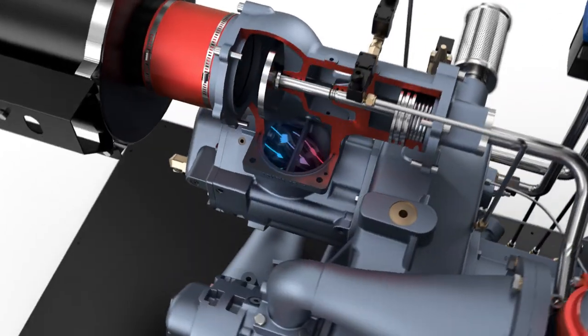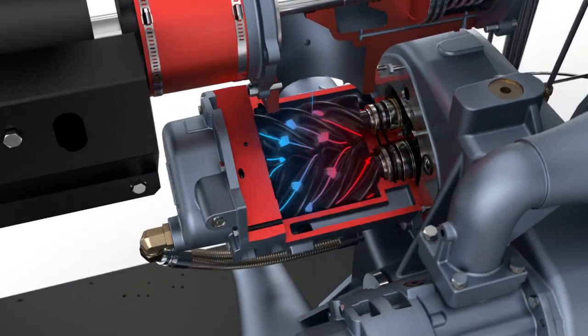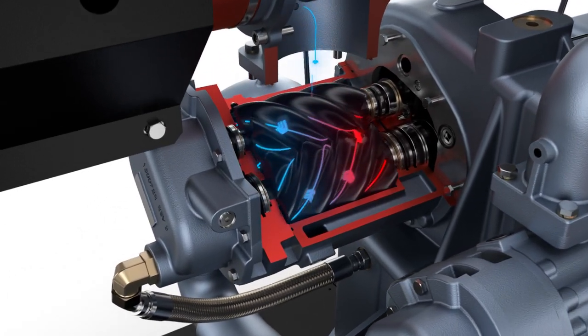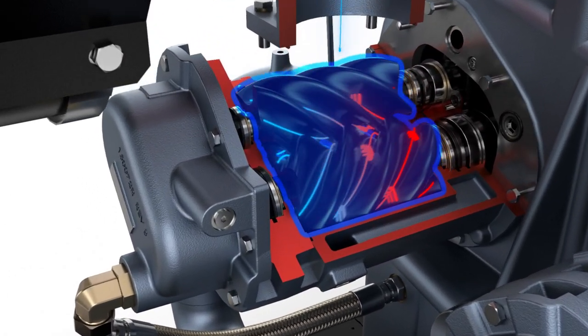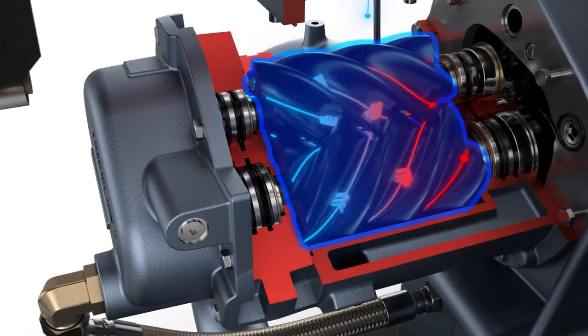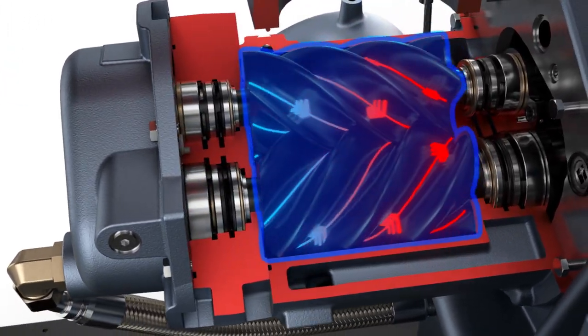Within the air end are two interlocking PTFE-coated rotors, machined to micron precision. As they rotate, the space between them gradually decreases, trapping the incoming air and steadily compressing it.